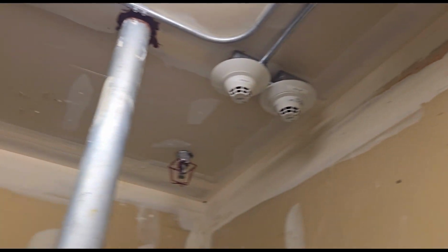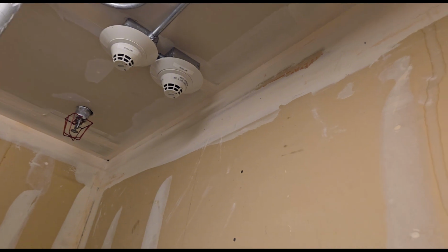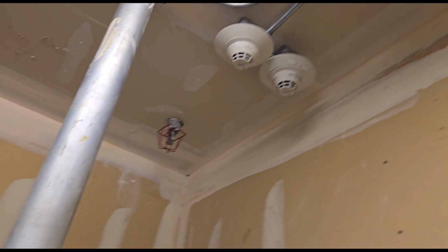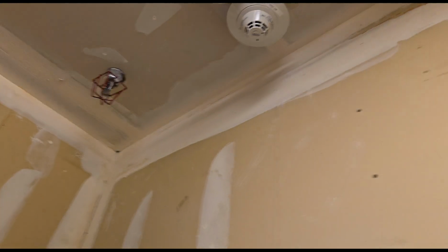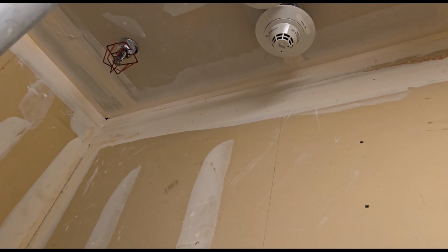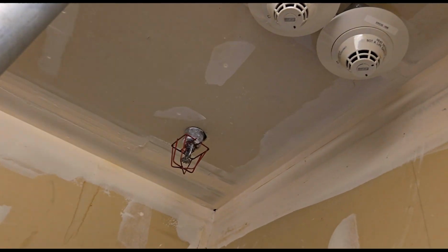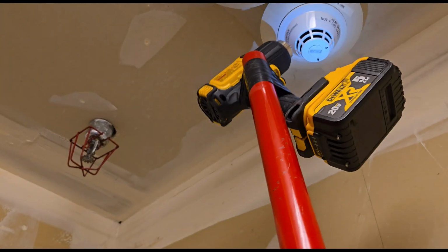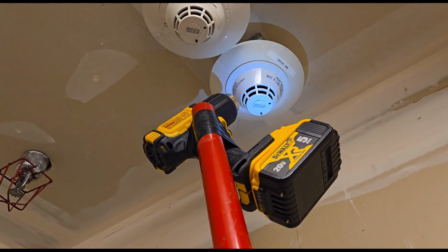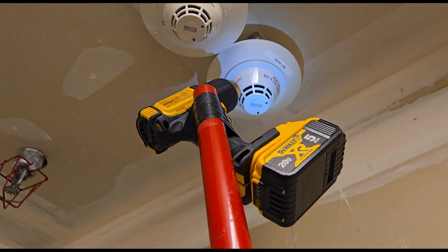And you always want to wait to make sure your elevator has fully recalled with the doors open. So the elevator is already on the correct floor because it hasn't moved. That way, if anyone's trapped inside, you wouldn't want them to lose power as you're about to hit this heat detector, which will flip the breaker and cause it to shunt. So now we'll do our heat, and I'm gonna not aim my heat towards that sprinkler head back there. I'm gonna aim it that way. I'm just gonna wave it so I try not to burn a spot into that heat detector.